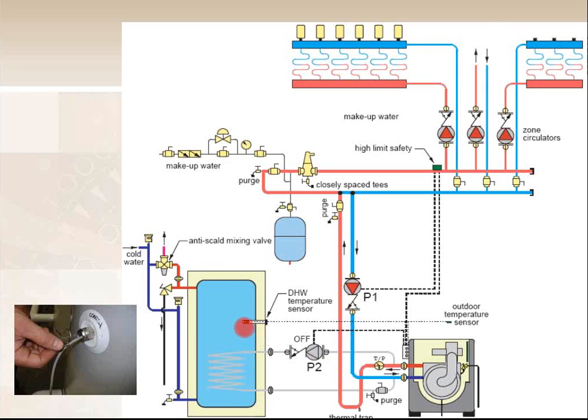So what happens when there's this domestic water sensor in here, and let's say I want to maintain 160 degree water. If the water temperature gets below that, that signal is going back to the boiler control. He says, well, you asked for 160 degree water, Ryan, but I see you only got 150. Maybe it's time to heat the domestic water. The boiler will tell pump number 1 to shut off, and then he'll tell pump number 2 to turn on. And then now my main loop looks like this guy here. Right, through pump 2, through this coil, and then return back to the boiler. Right, and all my water just going right from the boiler into this coil, heating up the domestic water.